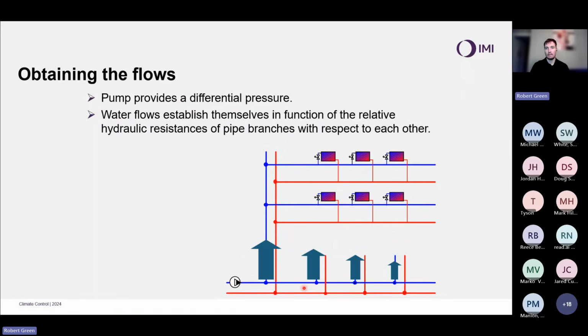My sources of imbalance being my pipe losses, they are, to be honest, one of the main losses in a system, my pipework and associated fittings. They are going to be causing these differences in available pressure to each area. And therefore, my difference in available pressure is going to have a dramatic impact on my flow. And the same thing happens at a terminal level. So on each floor, again, we can have excessive flow on the units closest to the inlet. And as we go further out on that floor, we have larger pipework resistance. We're going to get a consequently lower flow rate.